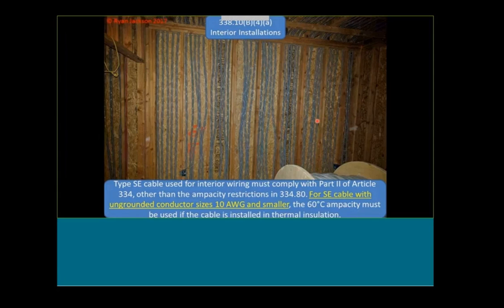Now it says, if you've got tiny SE cables—10 gauge and smaller, and by the way, I've never seen a 10 gauge SE cable in my life, I'm sure they make them, but I've never seen one that small—then that 60 degree rule applies. If it's a larger cable, which is all of them, then you can go ahead and use the 75 degree column, assuming that's what the conductors are rated for.